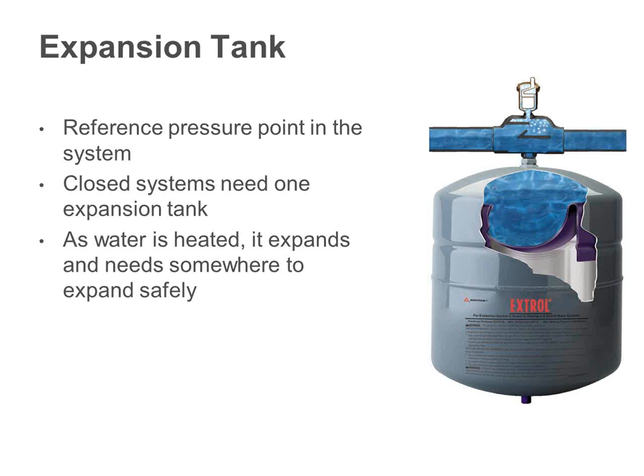Okay. Expansion tanks are one of the most critical parts of the system. They're definitely oversized most of the time, but they're also very hard for you to resize. Most of the tanks you'll be running into, in the boiler rooms we're talking about here today, are probably 25, 30, 40 years plus. They didn't have diaphragm tanks back then, okay? So basically an old steel tank, normally up in the top of the boiler room ceiling, might have gauge glasses on it if you're lucky enough, so you know what's going on in the system. Probably doesn't, okay? But the expansion tank is there because we are a closed loop hydronic heating system.